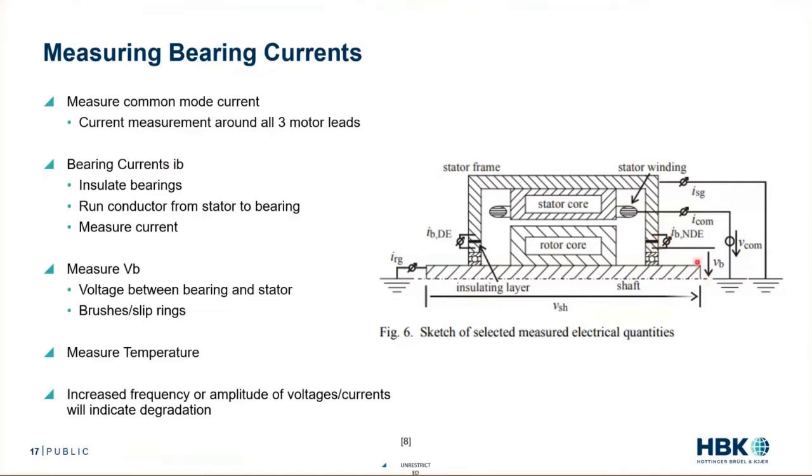I can also measure my bearing voltage. This one's a lot easier. I just put a measurement on the bearing and a measurement on the housing, and I look at that differential. So we can start to understand what is my bearing voltage, what is my bearing current. We can see that voltage creep up over time and then discharge through the bearing, creep up, discharge. And we can start understanding what are the currents that bearing would experience.